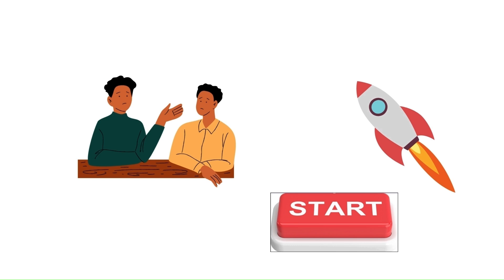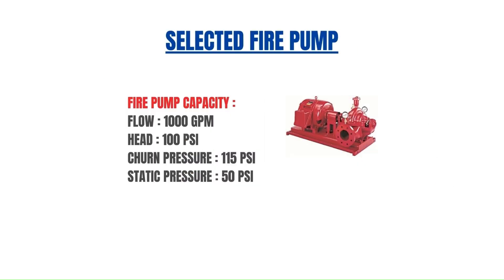Let us consider one example with a selected fire pump having a capacity of 1000 gpm at 100 psi, with a churn pressure of 115 psi. The static pressure available at the pump suction is 50 psi. Based on this data, we are going to determine the pressure settings for this particular pump.